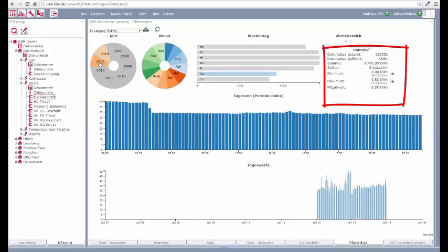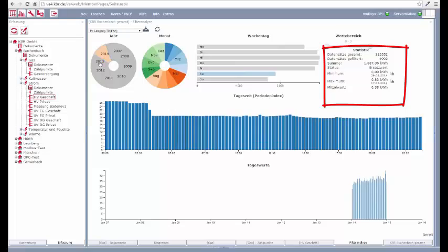In this example, the average daily consumption on a Saturday was 52 kilowatt-hours before and less than 36 kilowatt-hours after the measure was introduced. With a simple timer program, the daily consumption can be cut by nearly a third, which can be seen and quantified with a filter analysis.